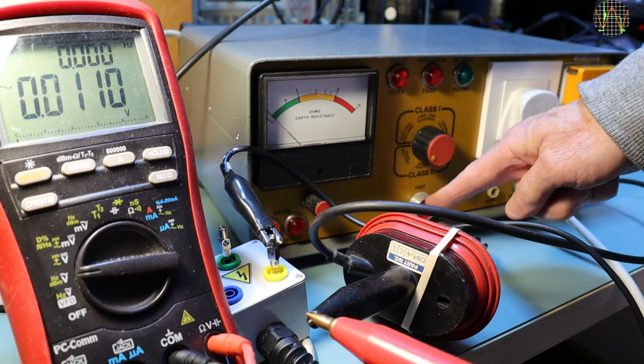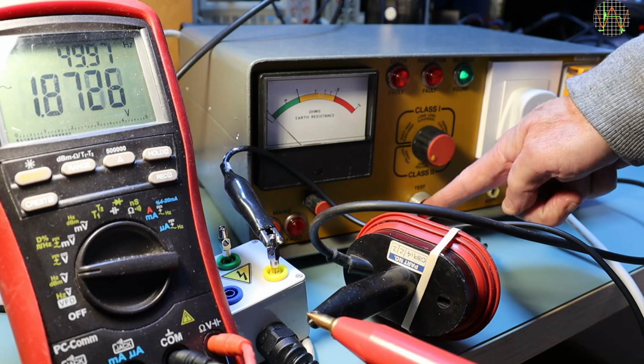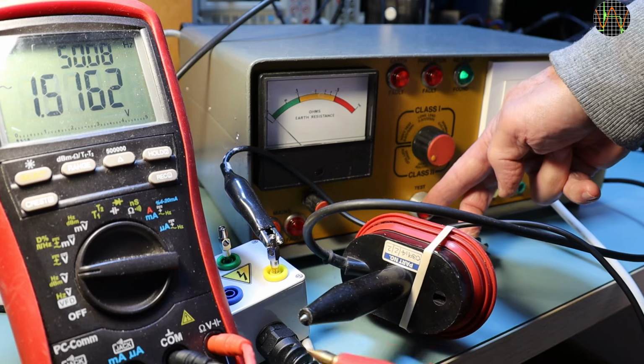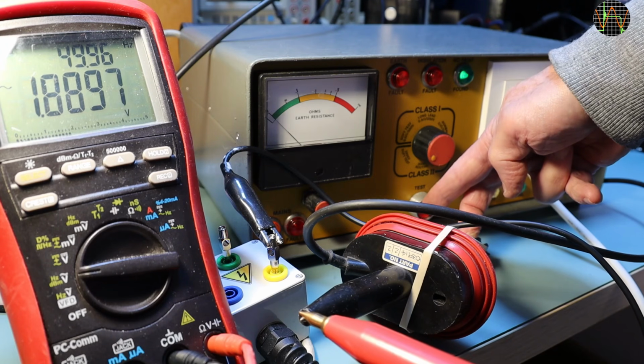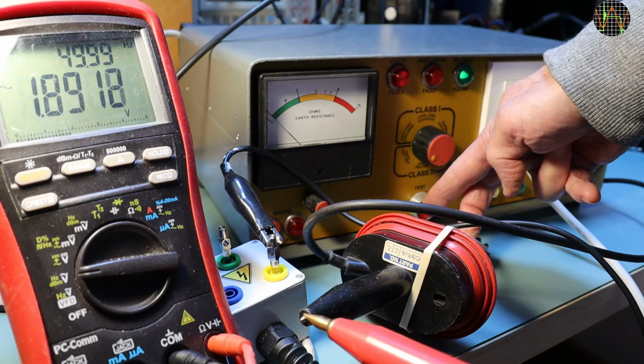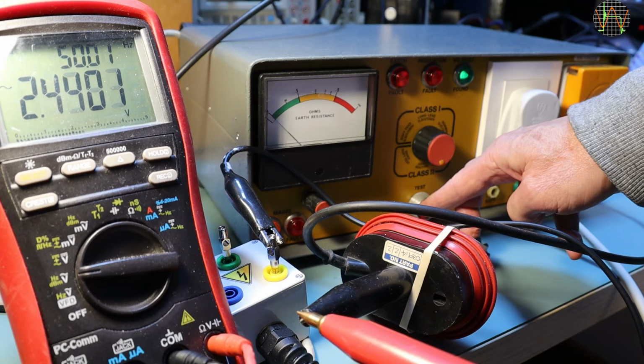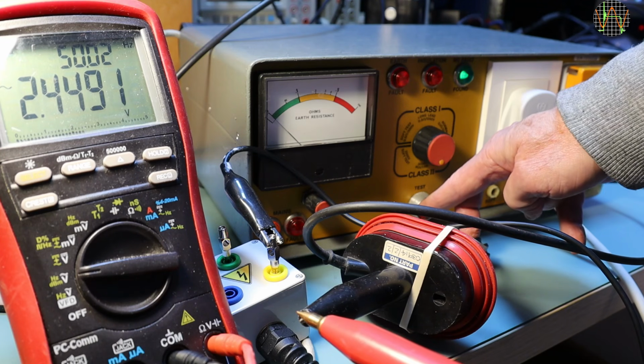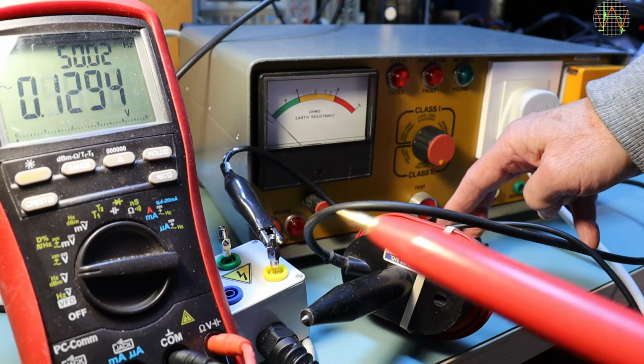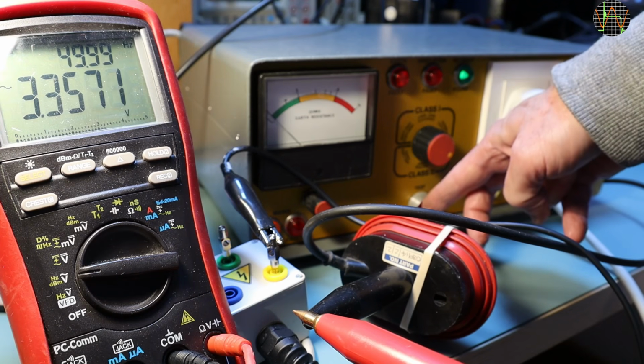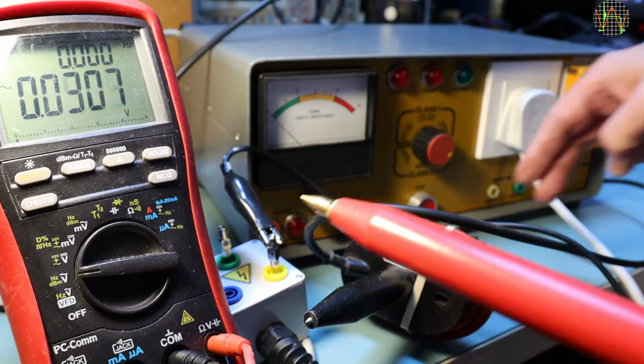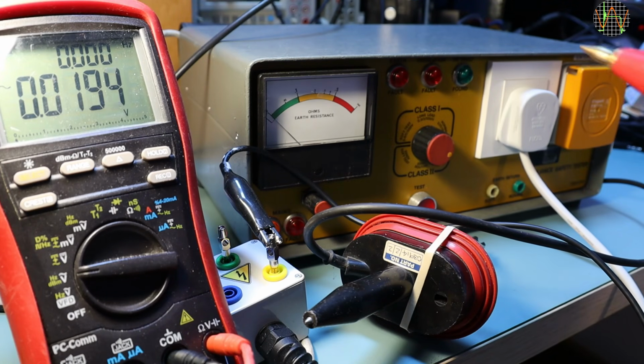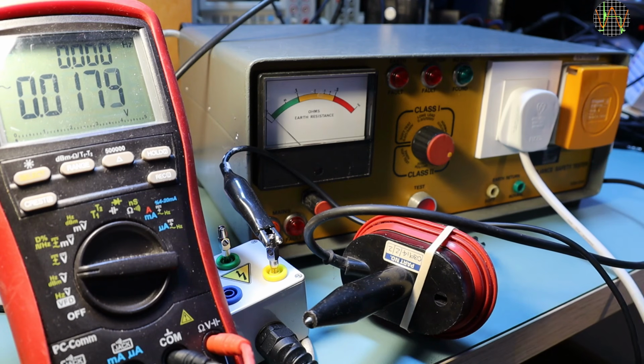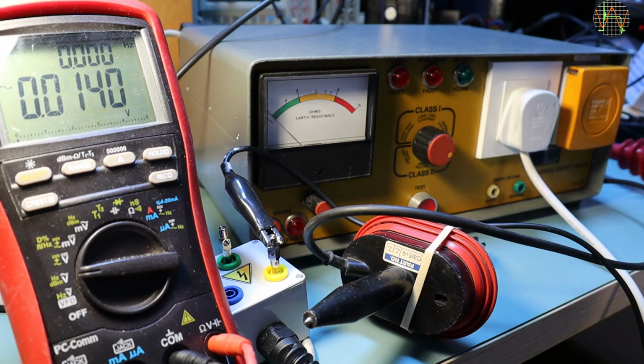Starting with the soft test, only about 1900 volts, not 2500. No doubt 1900 is plenty, but let's see if the others are also falling short. Indeed, the routine setting is only 2500 volts when it was labeled 3000, and the normal setting is only about 3400 volts instead of 3750. I still think these are way too high for using as a PAT tester with today's devices, but I would be interested if there's something not right or if this tester was tamed down a bit.